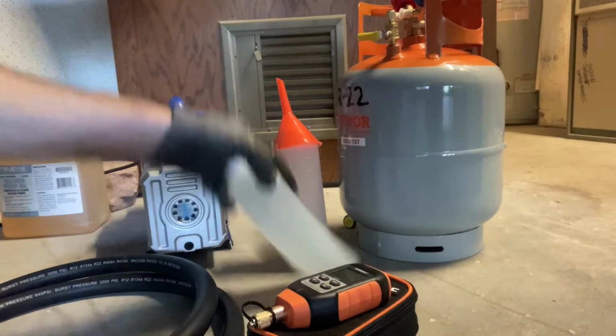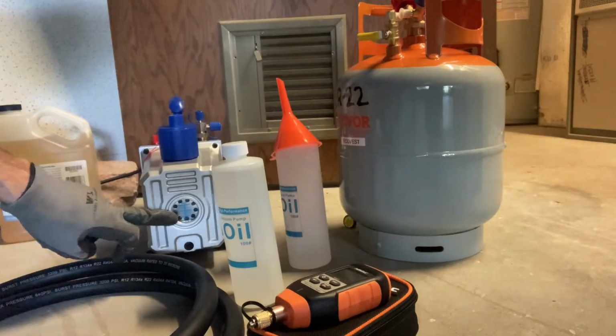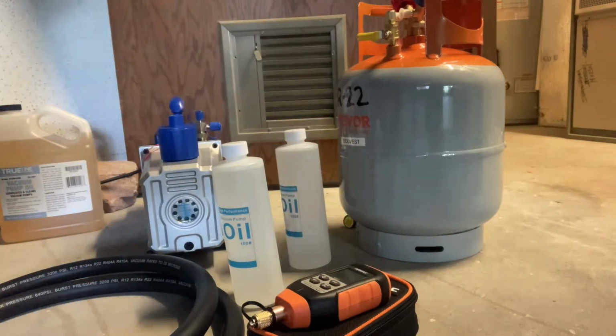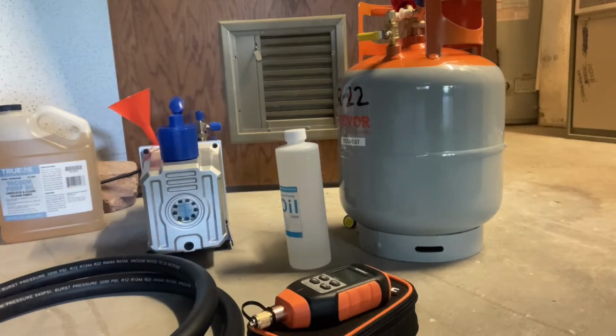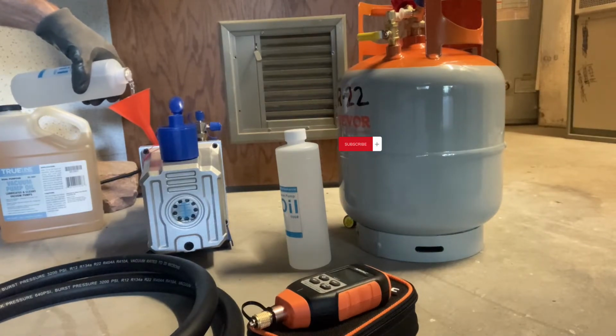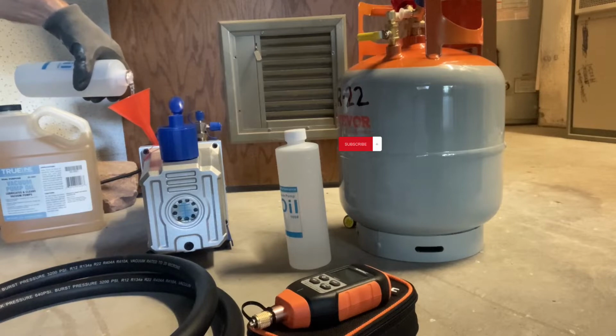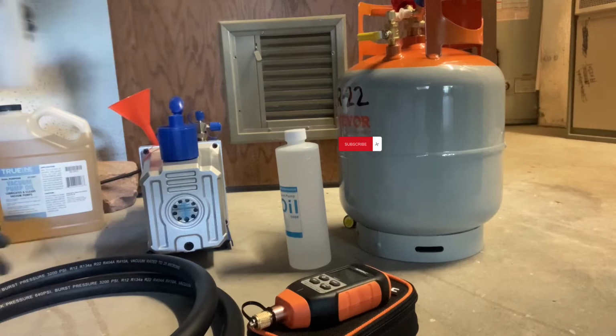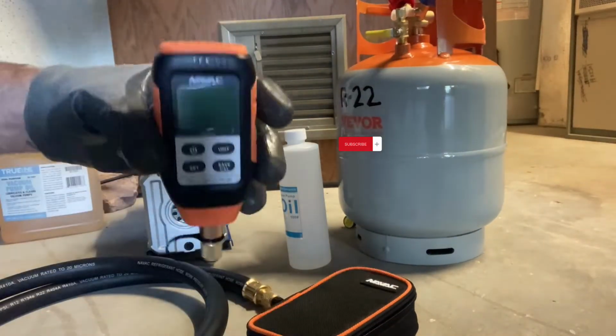So I'm going to start by pulling the vacuum on this brand new recovery tank. I'm using a brand new vacuum pump, so we're going to need to fill it up with vacuum pump oil before we can use it. If the vacuum pump oil is old, dirty, cloudy, milky, etc., you want to drain it out and put fresh vacuum pump oil in your vacuum pump. I'll also be using this digital vacuum gauge. And ideally, the larger and shorter your vacuum hoses are, the better when you're pulling a vacuum on a system. So there's our vacuum gauge.